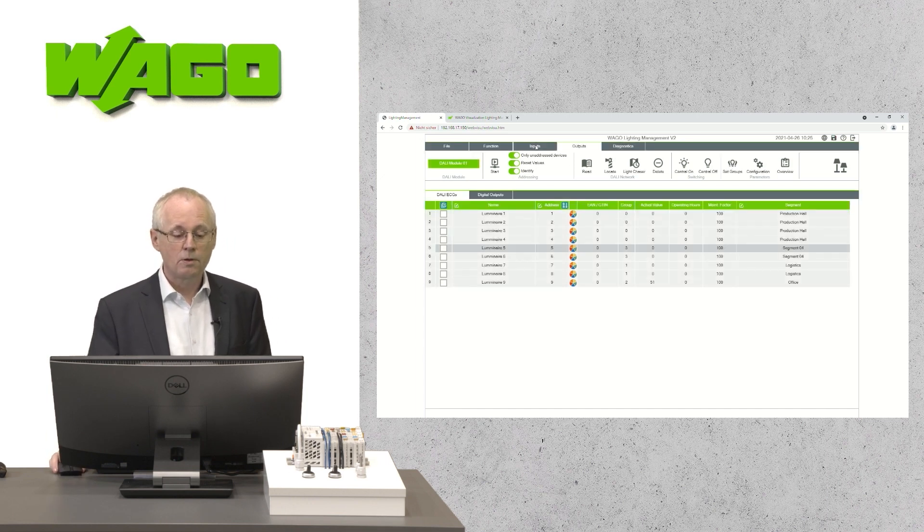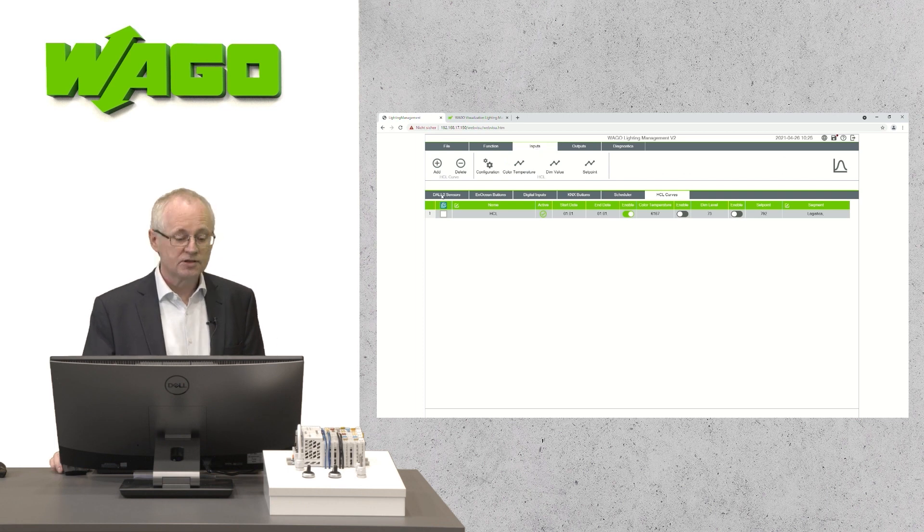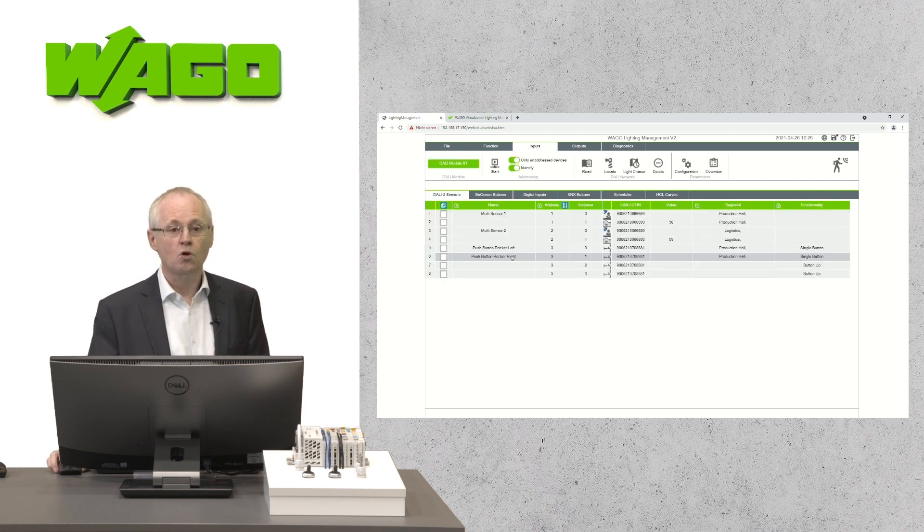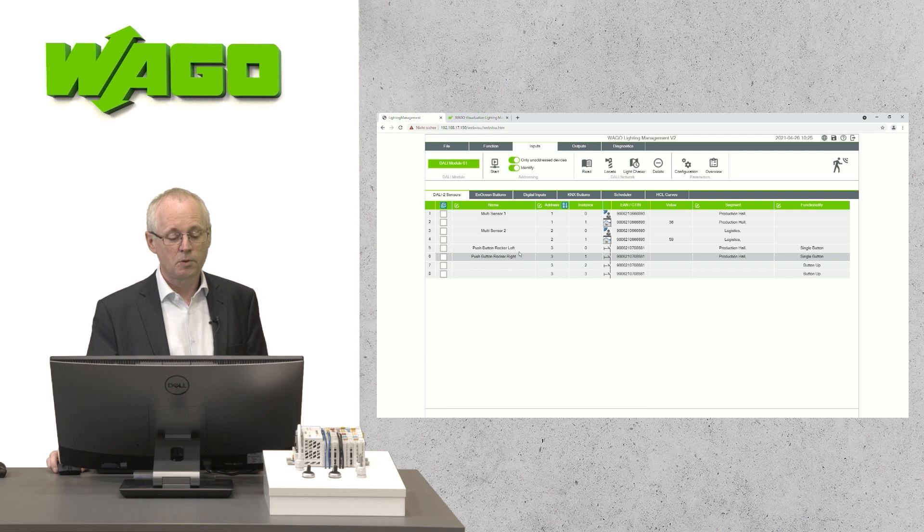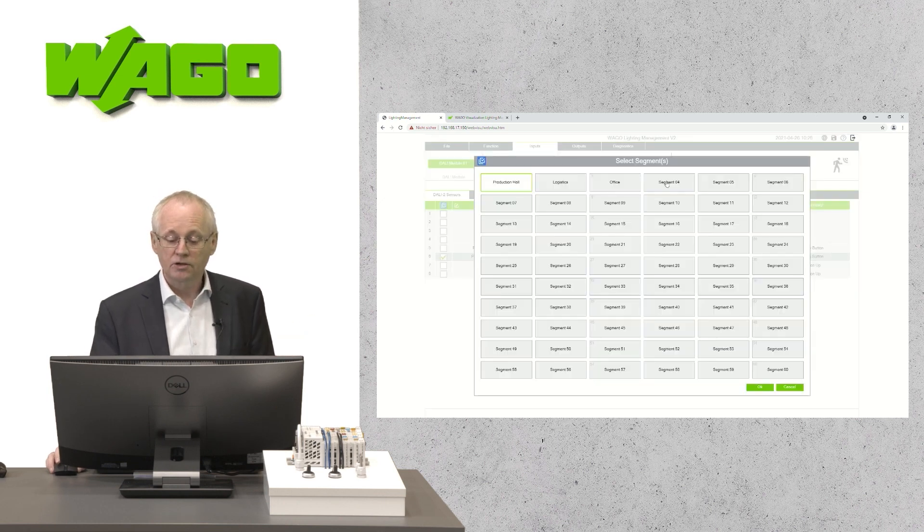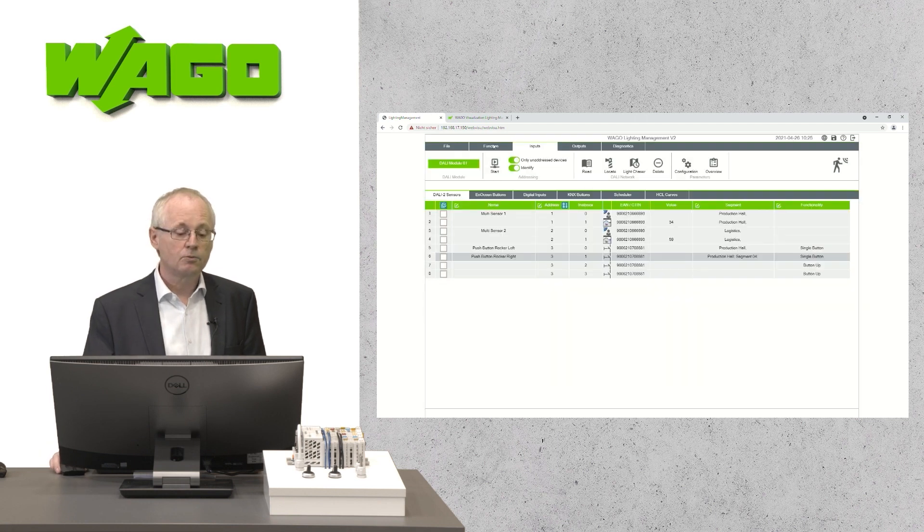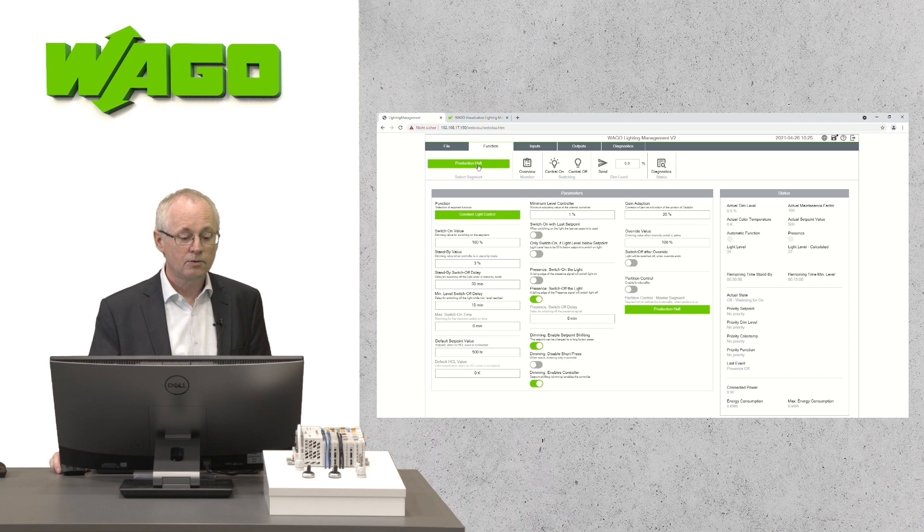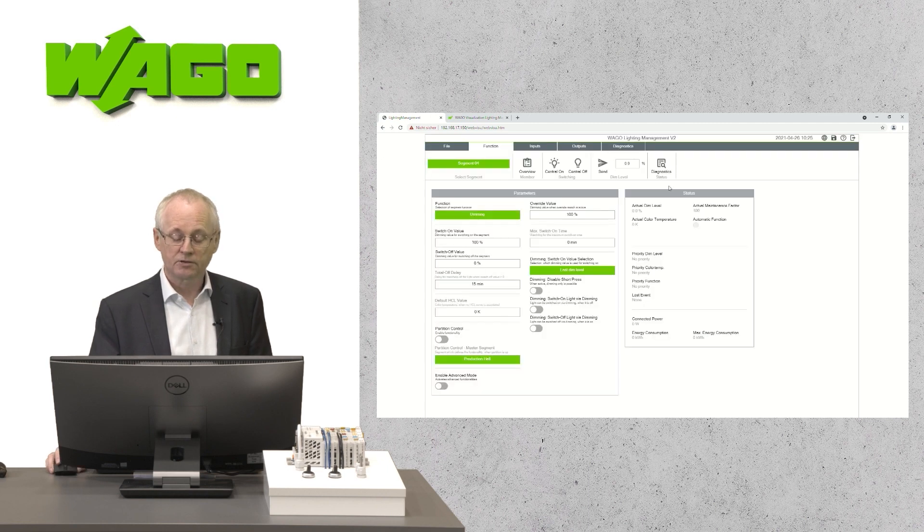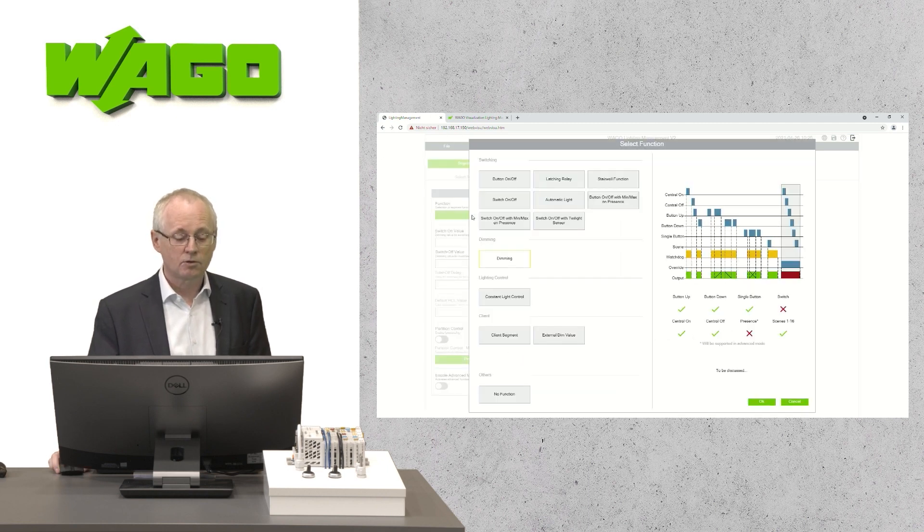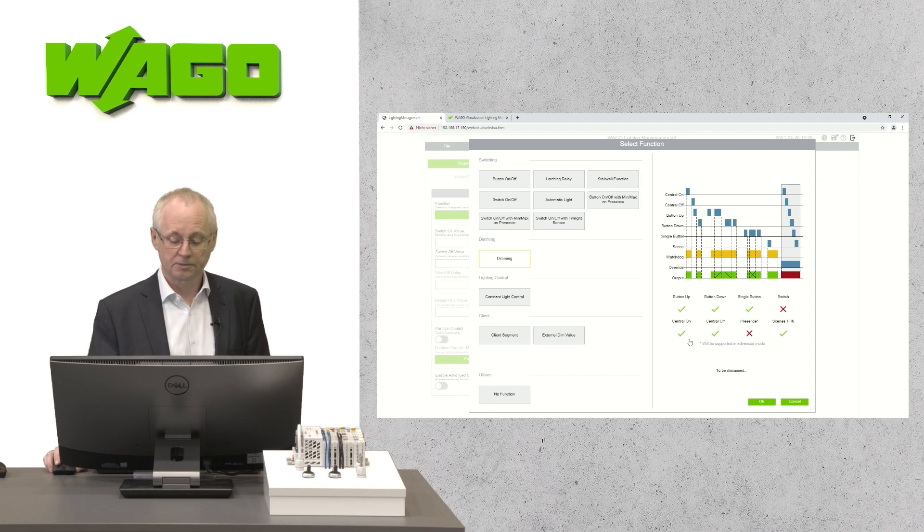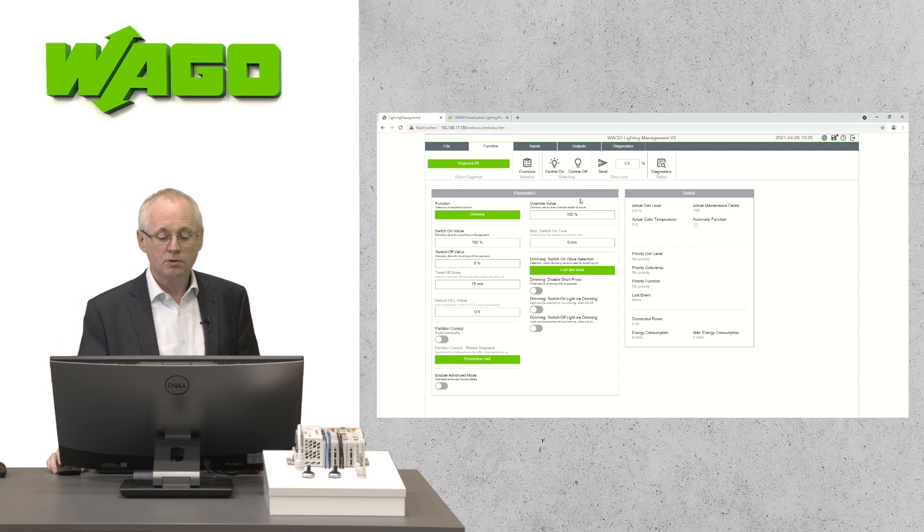After that, we will switch to the inputs. Select our DALI area, where we have a push button with two rockers. And we can use one of the rockers to switch the new segment on. After that, we will switch to the function area. We select the segment, the new segment and we can define a functionality for this new segment. For example, dimming. The reconfiguration is ready now.